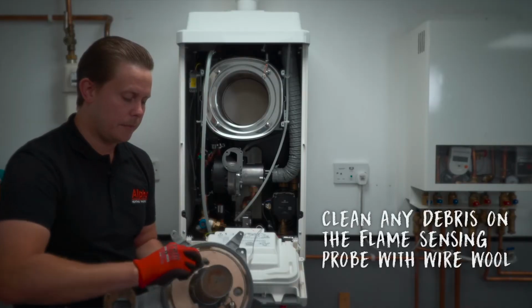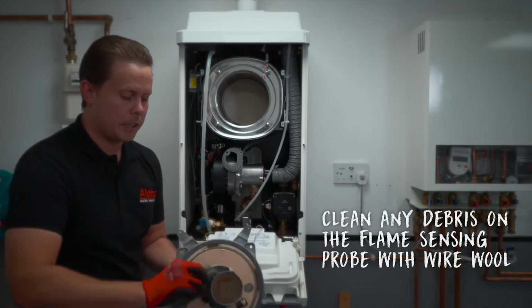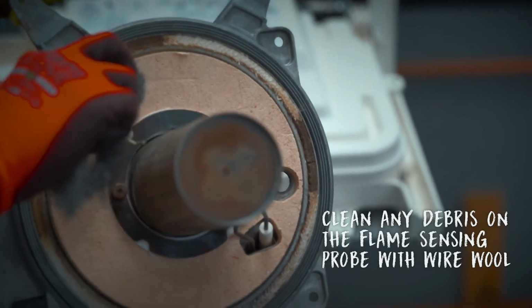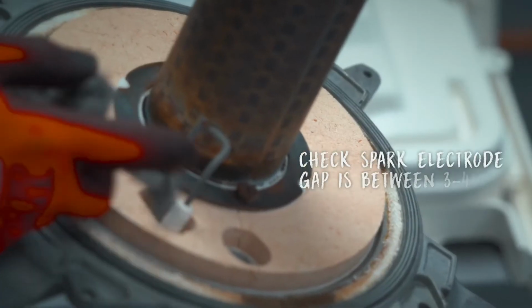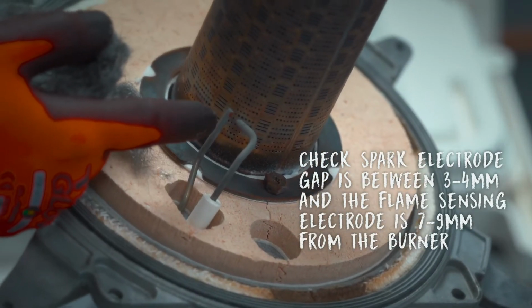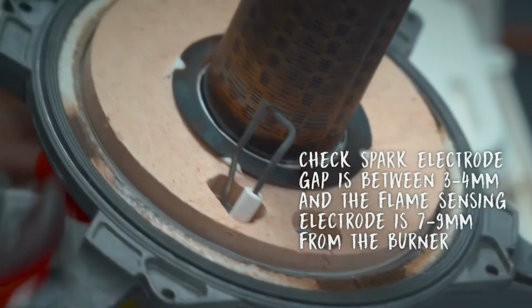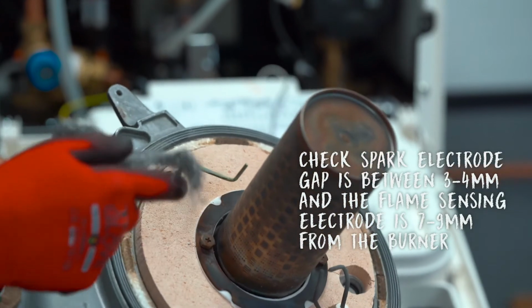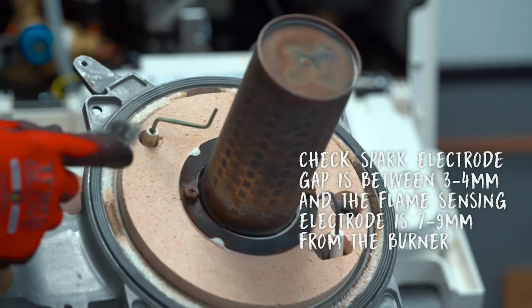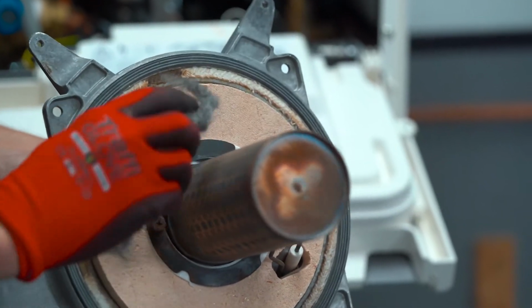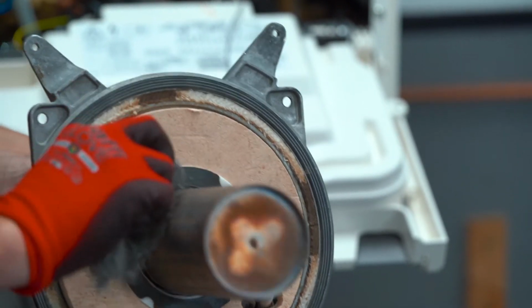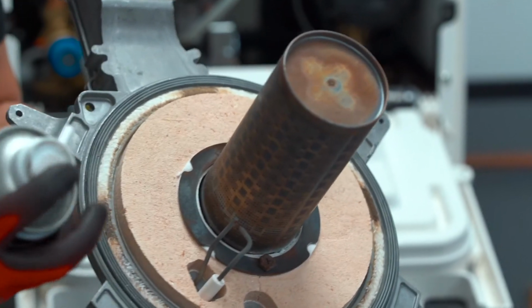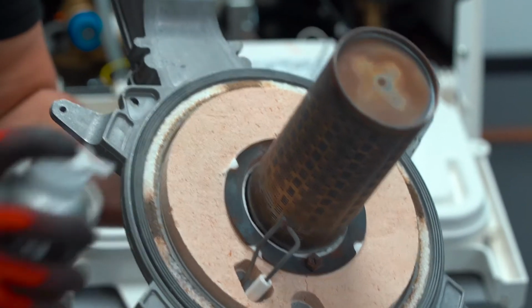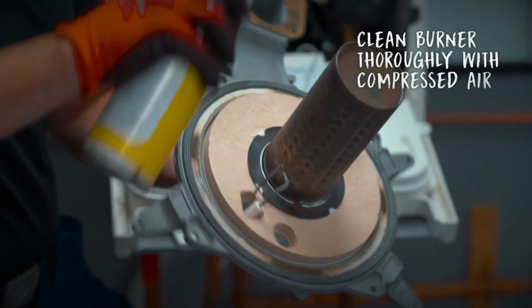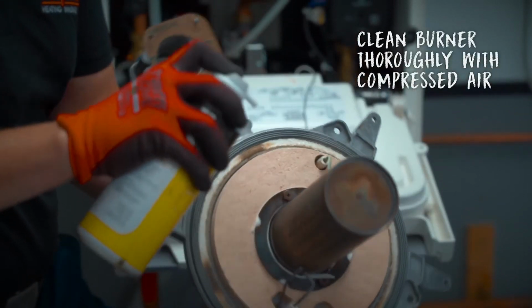The next step is to clean away any debris on the flame sensing probe with wire wool. You should also check that the spark electrode gap is between 3 and 4 mm, and that there is a 7 to 9 mm gap between the flame sensing electrode and the burner, before cleaning both electrodes with a suitable abrasive. Carry out a visual inspection on the burner and burner door seal for any signs of distress before thoroughly cleaning the burner with compressed air.